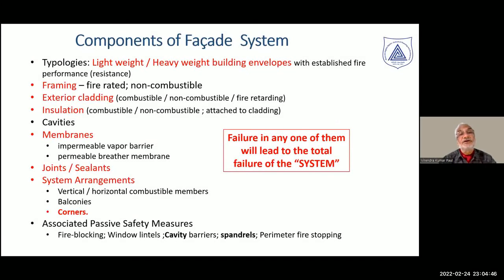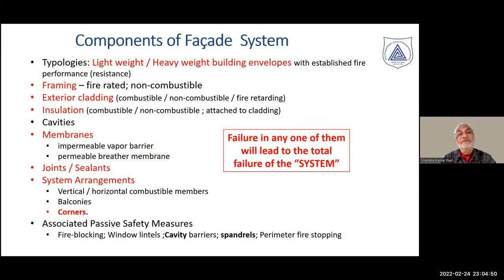Looking at the components of facades, we typically divide them into two categories: lightweight or heavyweight. In heavyweight building envelopes, thermally heavy material is used — the specific heat of the material moderates the external environmental conditions and temperature. The other type uses insulation properties, typically seen in high-rise buildings, where adding thermally massive envelopes can lead to structural complications. Heavyweight thermally massive envelopes are not suited for tall buildings — maybe four or five floors at most.